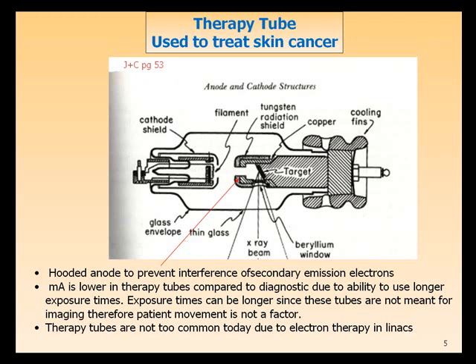The reason for having copper and then tungsten: the secondary electrons emitted from the anode are attenuated by the copper — electrons have charge and mass and are easily attenuated by copper and aluminum, so we don't need a high Z material for that. But those electrons interact with copper and create photons. We don't want leakage radiation, so we place a tungsten shield — tungsten has a high atomic number — to attenuate the photons created by the electrons.